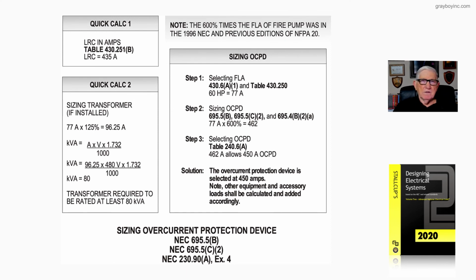large enough. That fire pump will operate to failure, but you only have to have the device sized so that it will operate to failure by the present codes, NEC and NFPA 20. And this illustration that we're looking at is sizing the overcurrent protection device in accordance with 695.5(B), 695.5(C)(2), and 230.90(A) Exception 4 will go along with this installation under certain conditions of use.